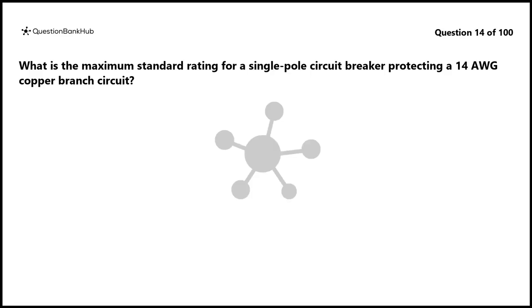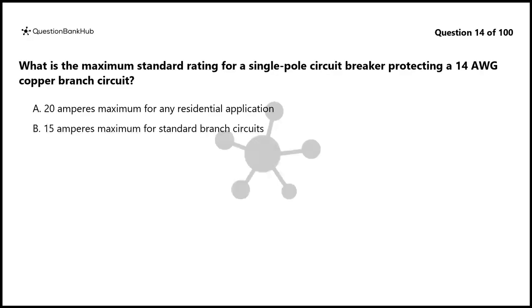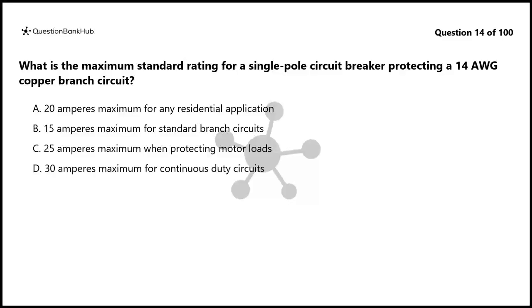Question 14. What is the maximum standard rating for a single-pole circuit breaker protecting a 14 AWG copper branch circuit? A. 20 amperes maximum for any residential application. B. 15 amperes maximum for standard branch circuits. C. 25 amperes maximum when protecting motor loads. D. 30 amperes maximum for continuous duty circuits.